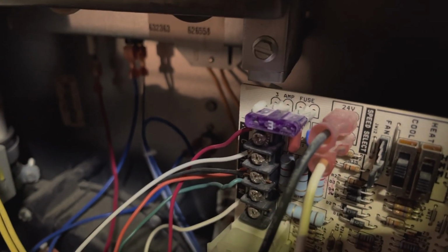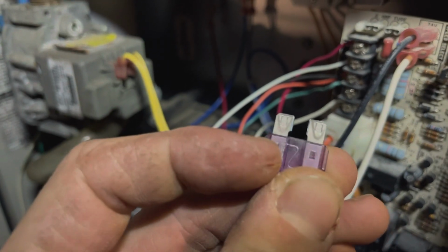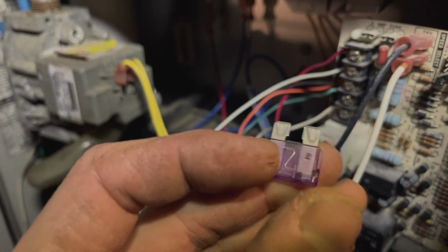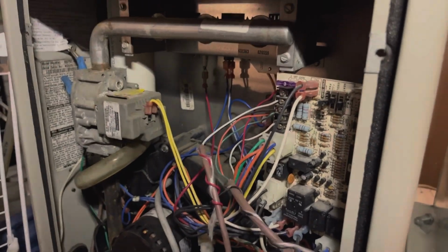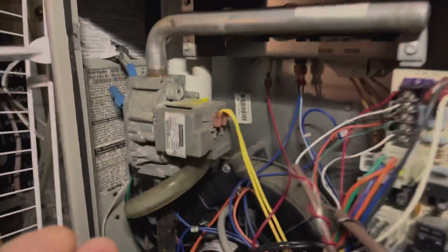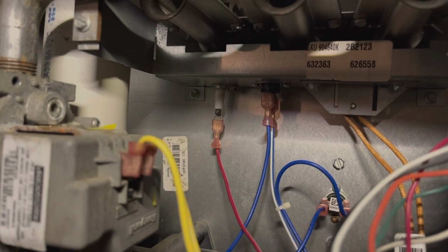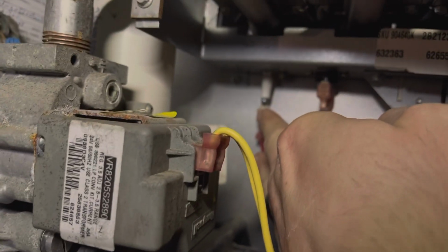And then one of your other possible causes could be this 3 amp fuse right here. So with your power off there, you can check, you'll see that will be burnt and blown. That's not our issue. Now, I'm going over issues that we don't have, but it could be the problem. Now, another common issue that could happen is this right here. This is a maintenance thing you can do.